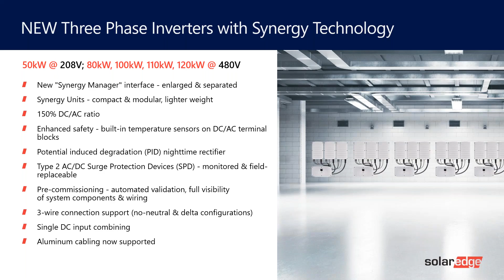So this is the close-up of the Synergy unit. I already covered a lot of the detail, but you can see this particular inverter could be a 50 kilowatt, 100, 110, or 120. You have the 3 Synergy units on top, and the Synergy Manager on the bottom. The Synergy Manager is where all your connections are, including your DC wiring, plus and minus, coming off your solar panels.